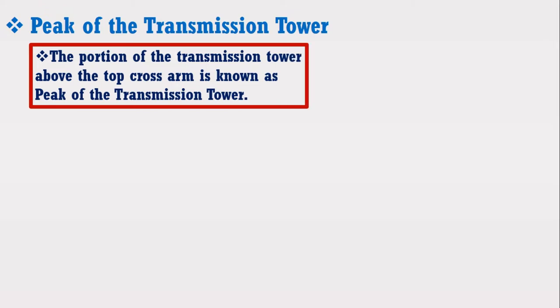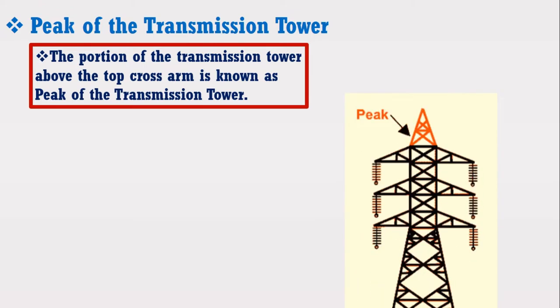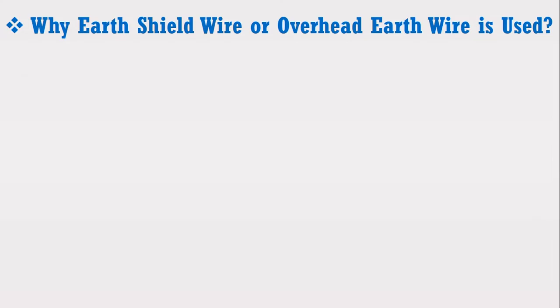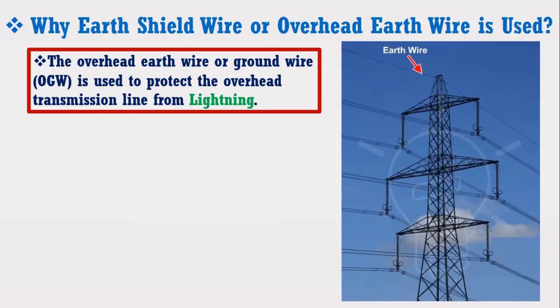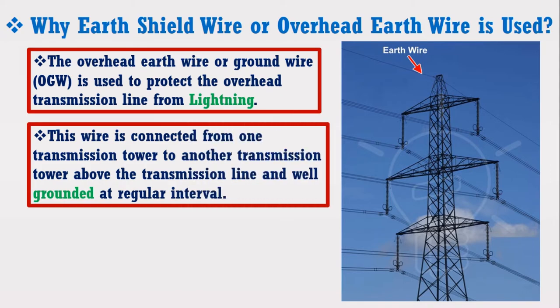Now I am going to discuss about the peak of the transmission tower. It may be defined as the portion of the transmission tower above the top cross arm. The earth shield wire is connected at the tip of this peak. The overhead earth wire or ground wire is used to protect the overhead transmission line from lightning. Consider the figure in which the arrow shows the earth shield wire connected at the tip of the peak. This wire is connected from one transmission tower to another above the transmission line and is well grounded at regular intervals.